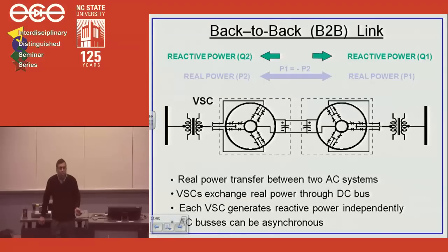And one more combination is that we can connect both of these electronic converters in shunt with two systems. Now we've got one more flexibility, which is that this transmission system is decoupled from this other transmission system. Why would you want to do that? We've got two AC circuits, right? Just think of very simple circuits. Frequency is different. Yeah, so if there is any difference in frequencies between the two circuits, then this kind of arrangement is absolutely required.